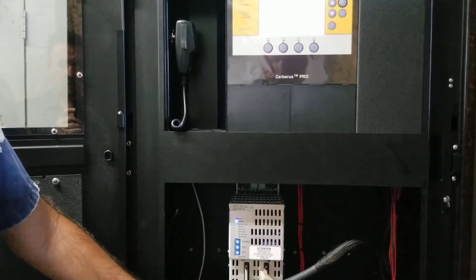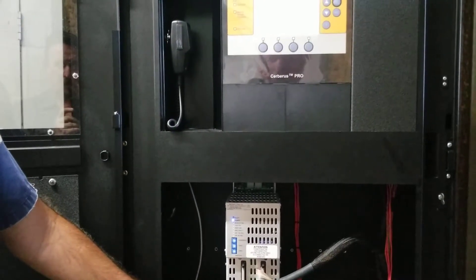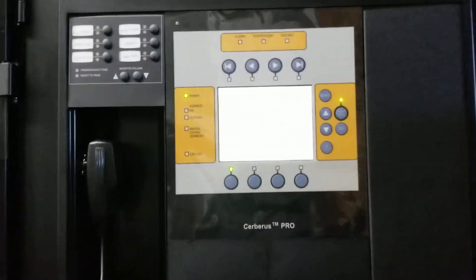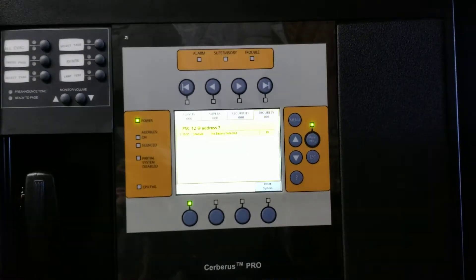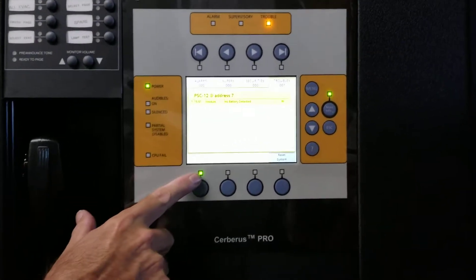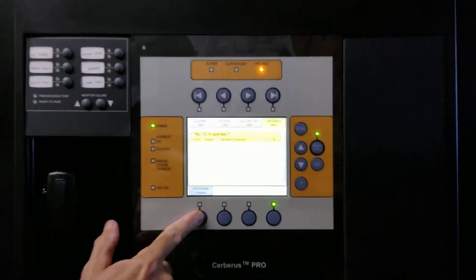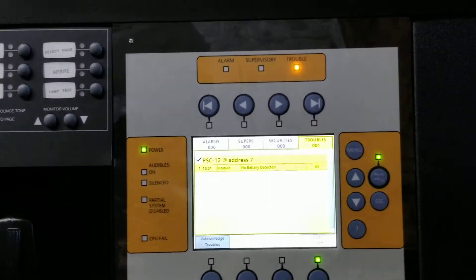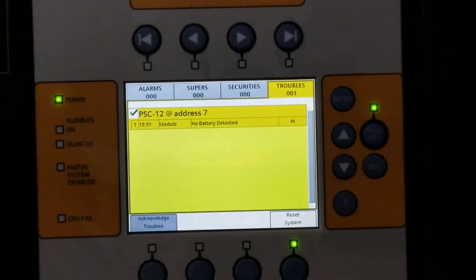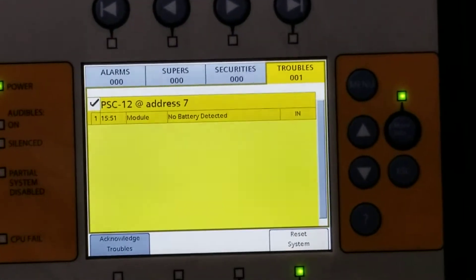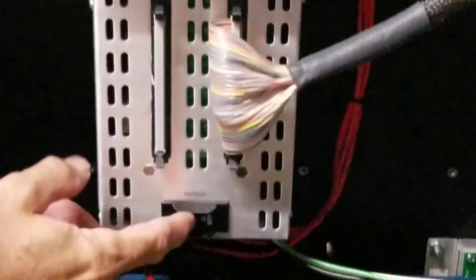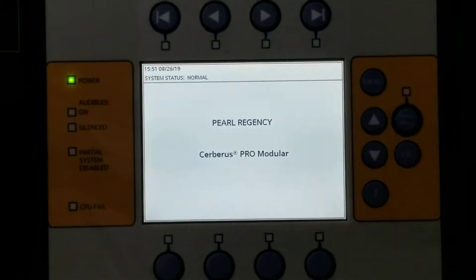Just to let you know, that's just the breaker for the battery — all I did was disconnect the battery. So here's a trouble. It's the same thing — it's highlighted. Acknowledge troubles, and it quits the beeping. Let's correct the problem. As soon as I corrected the problem, it reset itself and went back to the main screen.